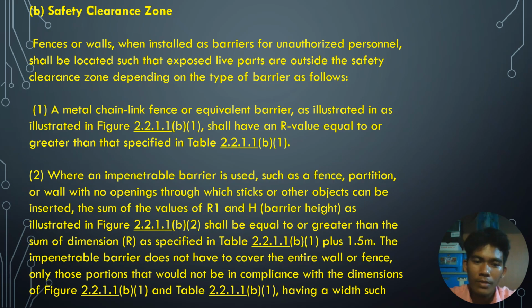The sum of the values of R1 and barrier height as illustrated in Figure 2.2.1 shall be equal to or greater than the sum of dimension R as specified in Table 2.2.1 plus 1.5 meters. The impenetrable barrier does not have to cover the entire wall or fence.